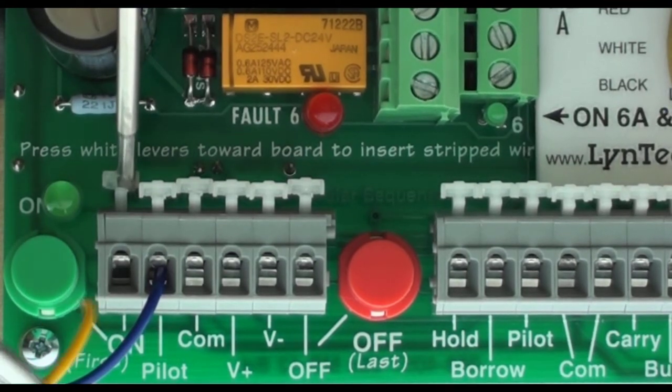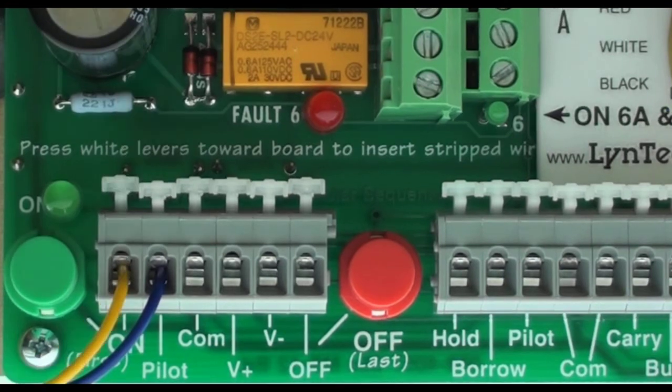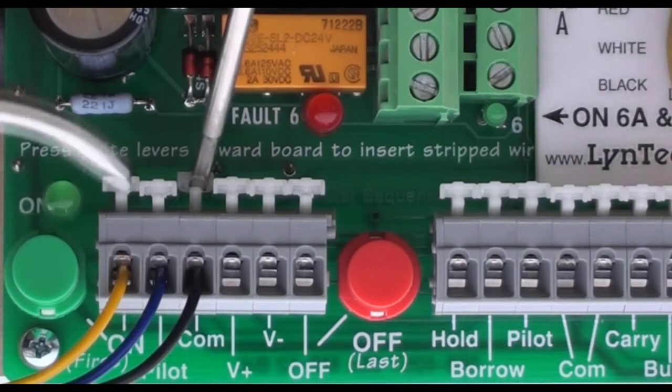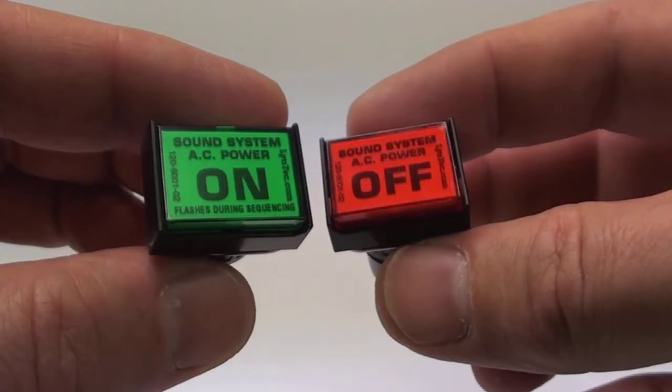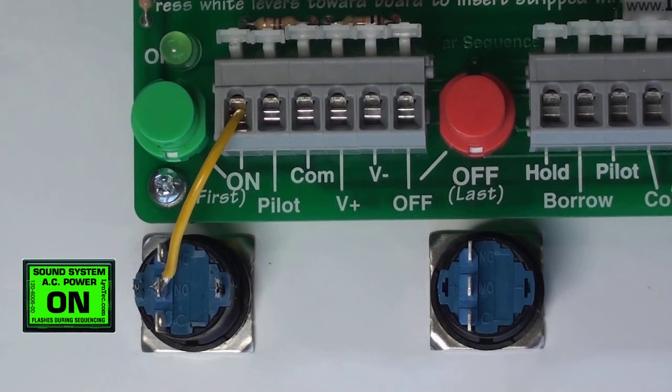Now that you've verified the system is working properly, you're ready to hook up the remote control wiring. Interface wiring is terminated on the circuit board via cage clamp style connectors. Press the white lever toward the circuit board to open the jaws of the connector, then insert the stripped wire. The switches that come with every LynTec sequencer are a momentary single-pole double-throw type, offering a set of normally open and normally closed contacts. We'll be using the normally open contacts.